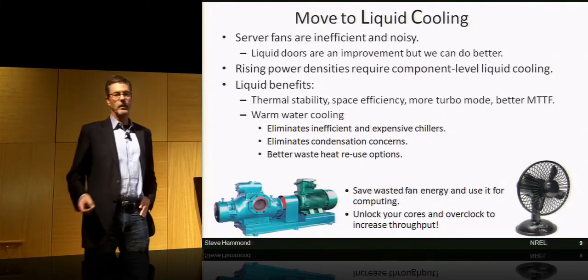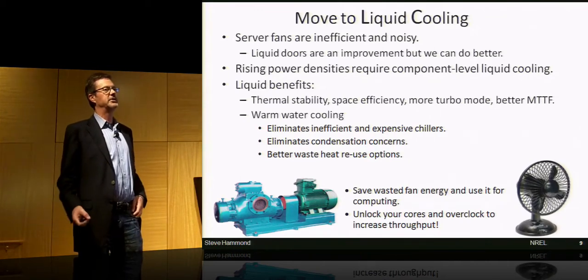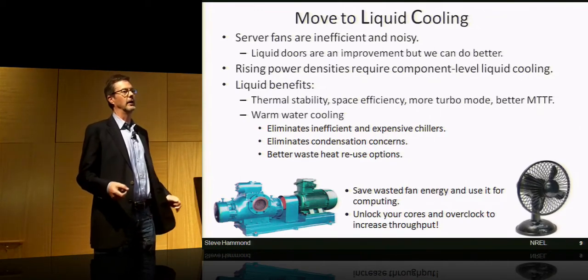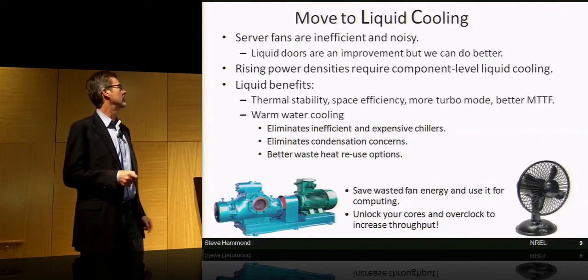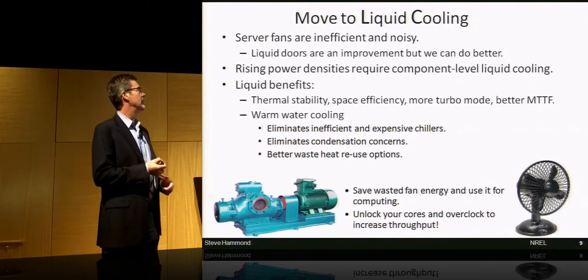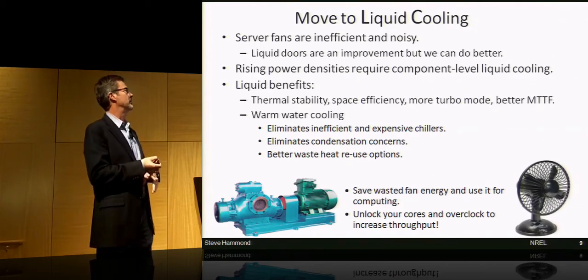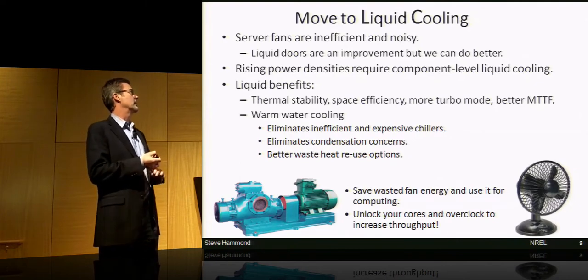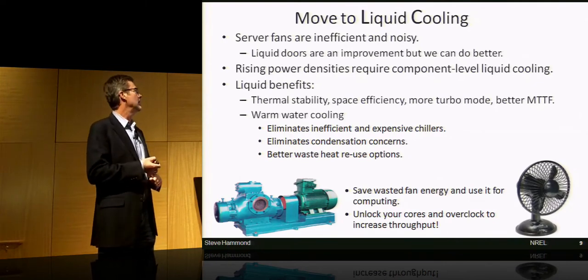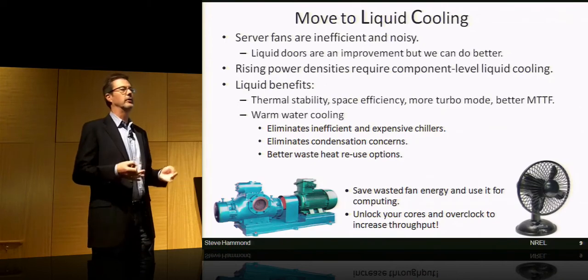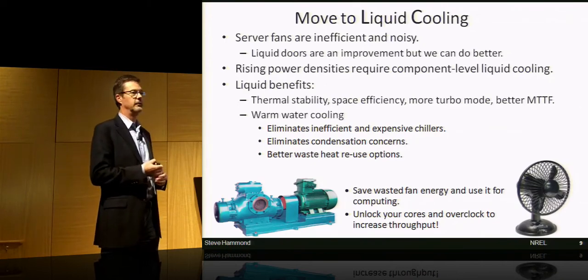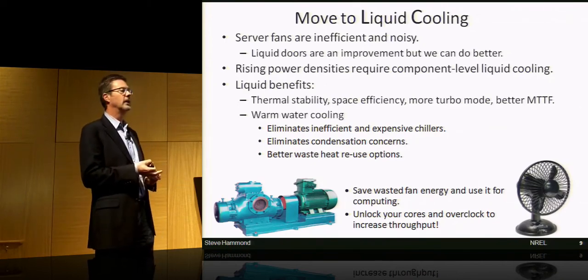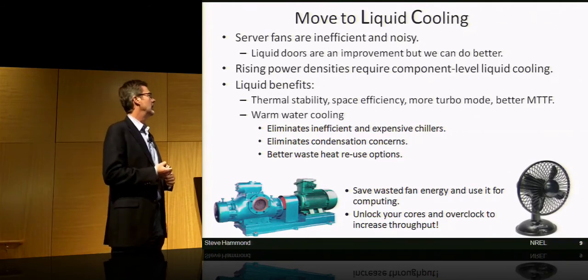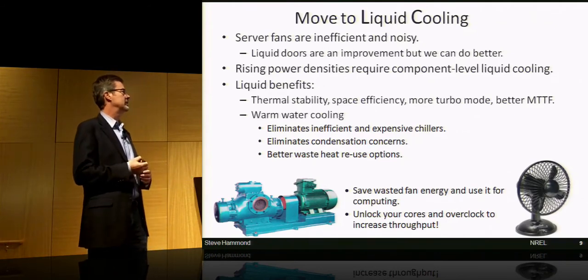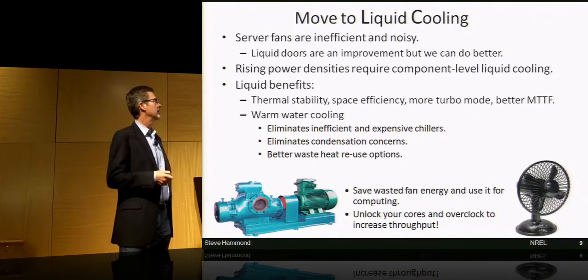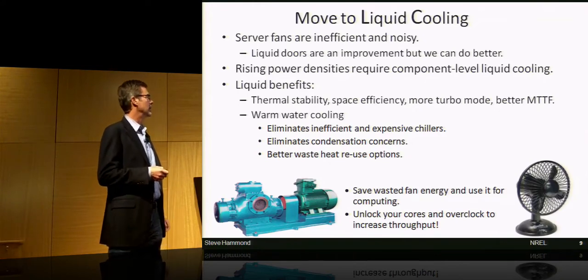So we made the decision in 2006 that we were going to move to liquid cooling, and that drove our data center design considerations. We thought a lot about liquid cooled doors. Those are good, but you often need much colder supply temperatures than if you did direct component level liquid cooling. So clearly we can do better. Rising power densities do require component level liquid cooling.